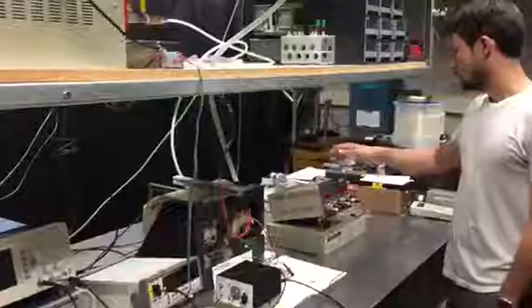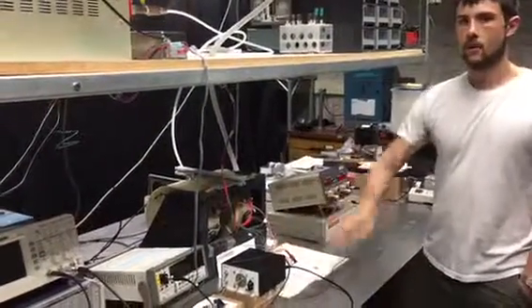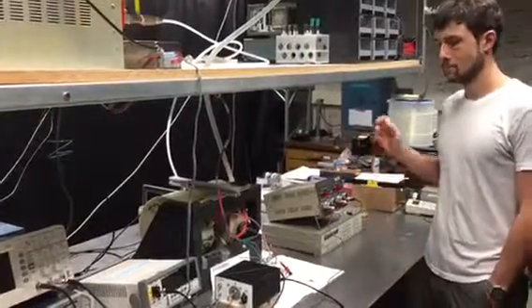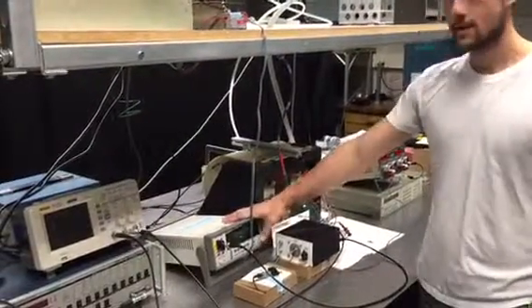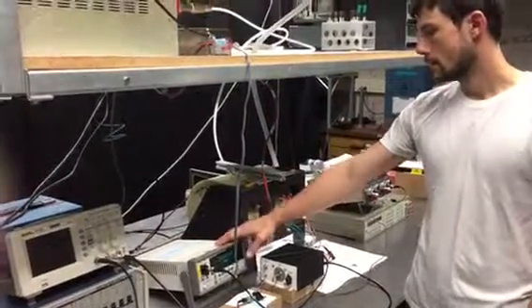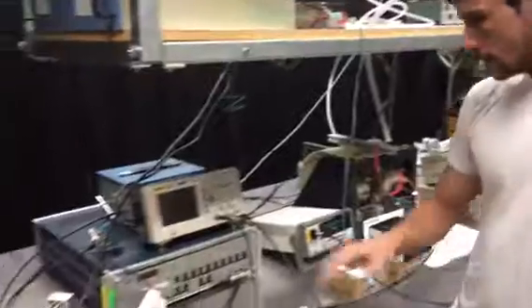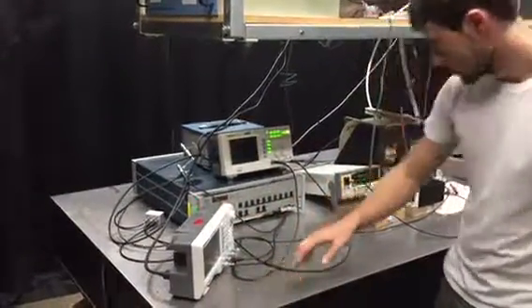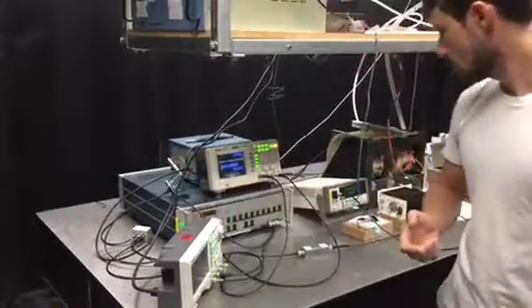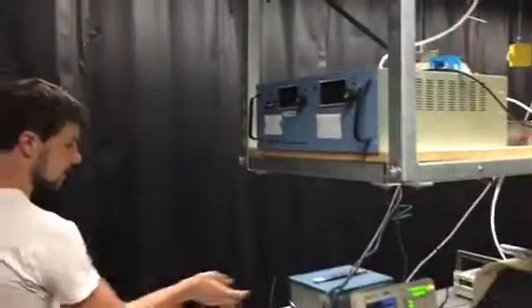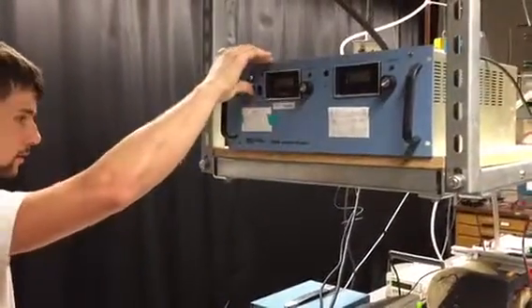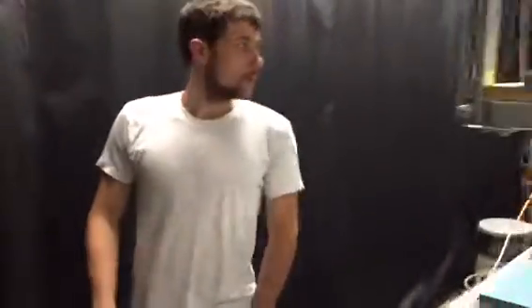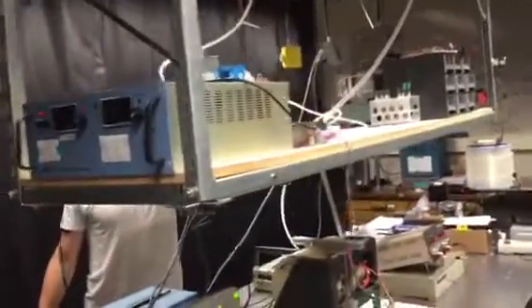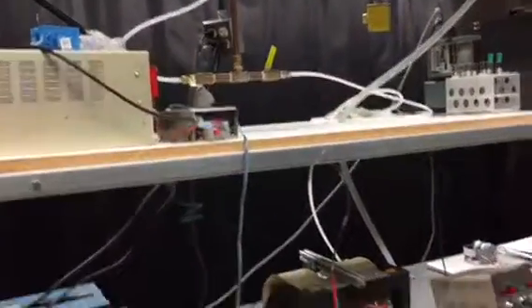And so pretty much the first step is to just go along and turn everything on. This guy takes about half an hour to completely warm up and stabilize, so that's been left on. If it's cold, this guy also takes about an hour to warm up to rated accuracy. It's still actually warm. So just go around, press the on button on everything. And it's about to get noisy. And don't forget to turn the water on, because this magnet will overheat if you don't.